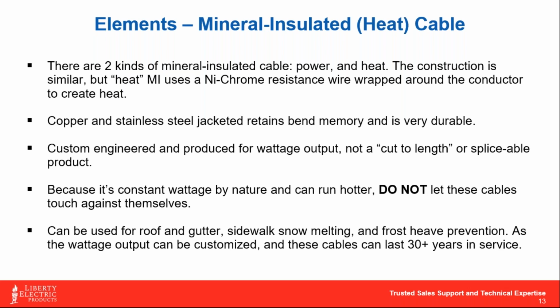This is a great permanent type of solution cable. We use it predominantly embedded in concrete for sidewalk snow melting applications, but it also works wonderfully in roof and gutter applications, especially with older historic buildings that have slate and copper roofs. We can actually get the copper jacketing of the cable to variegate or turn green, the same oxidation process you'll see on copper flashings and gutters on these historic buildings. The nice thing about this cable is it's extremely resilient - this is a product that could last 30 plus years.